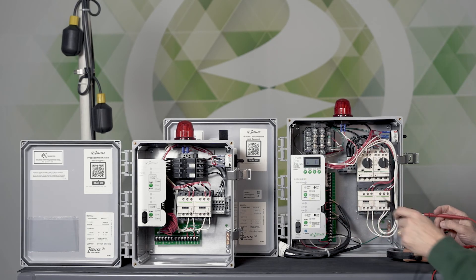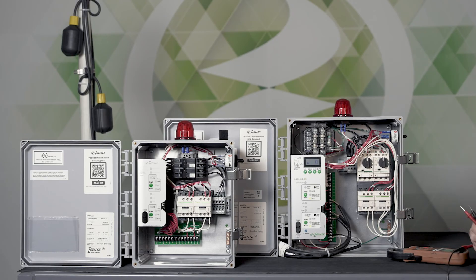Those would be your normal voltages. I provide that info for troubleshooting float switches — if you're getting different voltages than what we just showed, that may be a reason for the problem you're having, and something may be wired incorrectly. We'll have the other video about how the float logic works coming up.